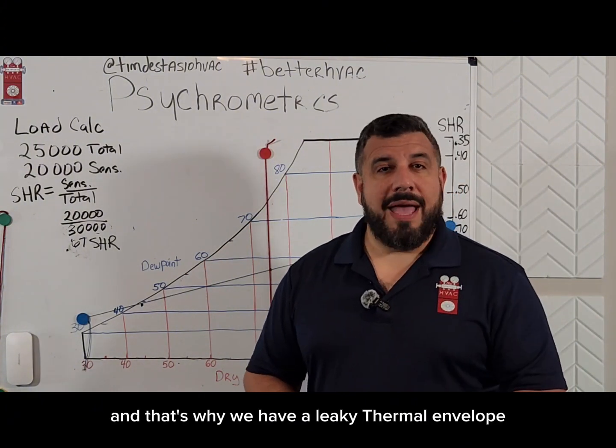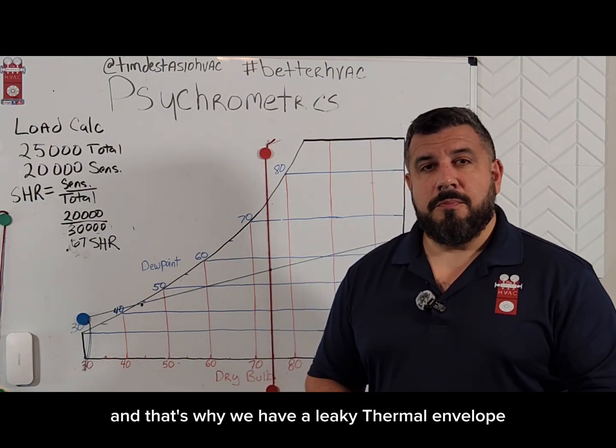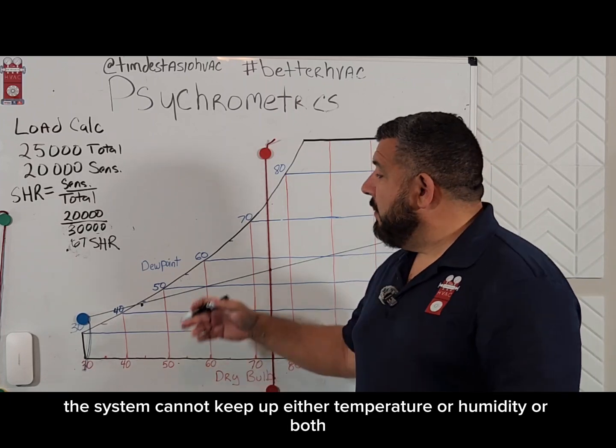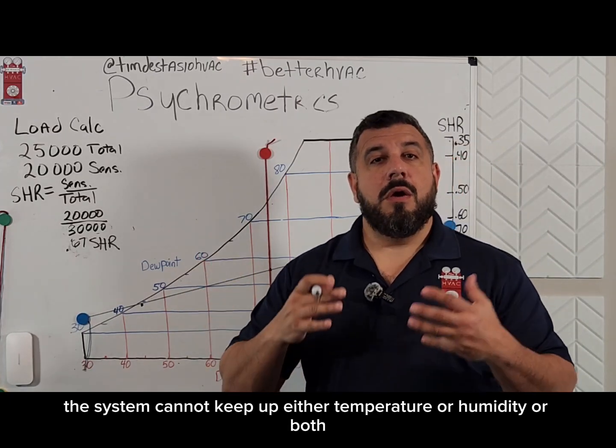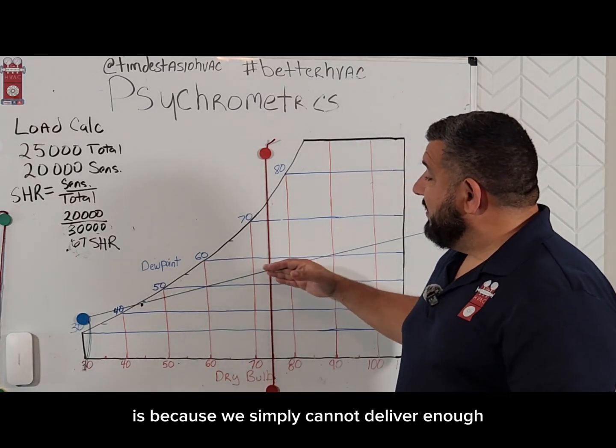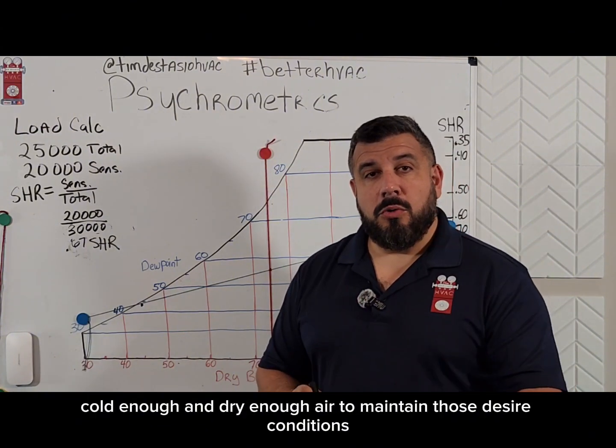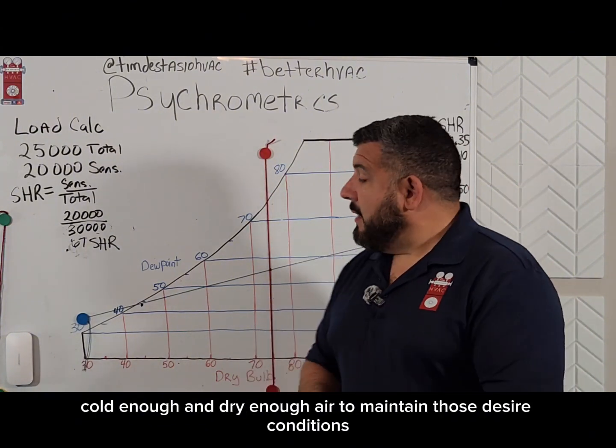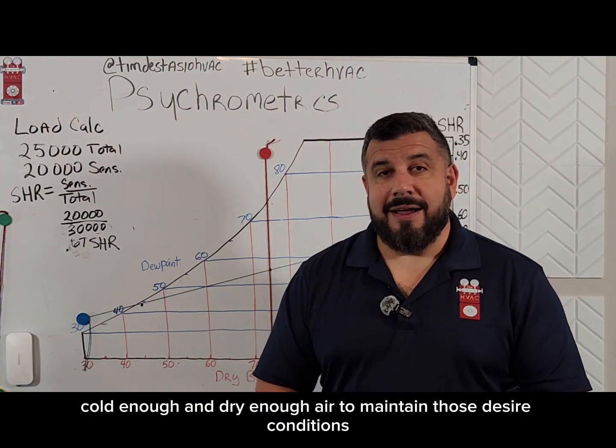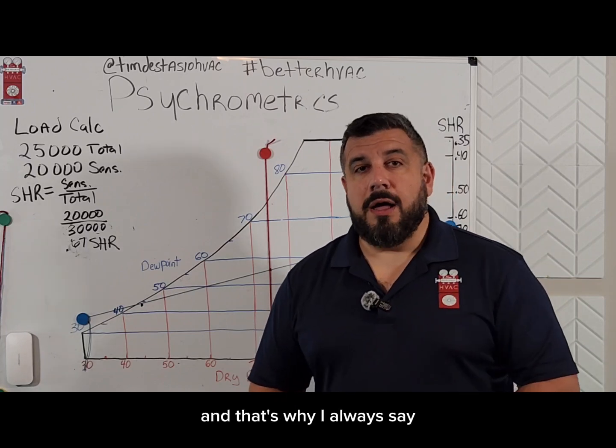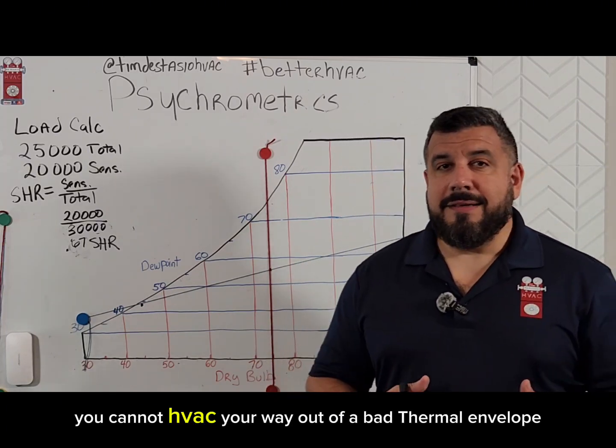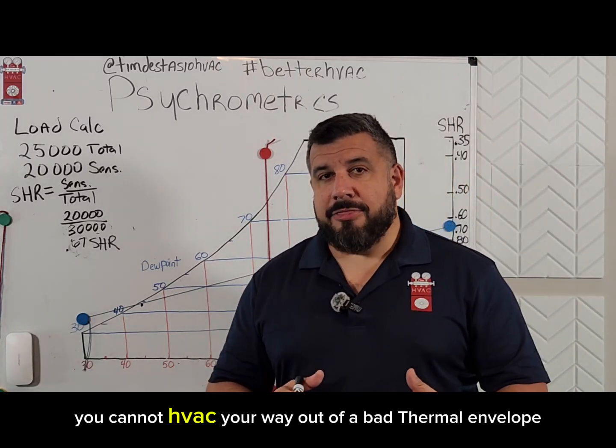And that's why when we have a leaky thermal envelope, the system cannot keep up either temperature or humidity or both. It's because we simply cannot deliver enough cold enough and dry enough air to maintain those desired conditions. And that's why I always say you cannot HVAC your way out of a bad thermal envelope.